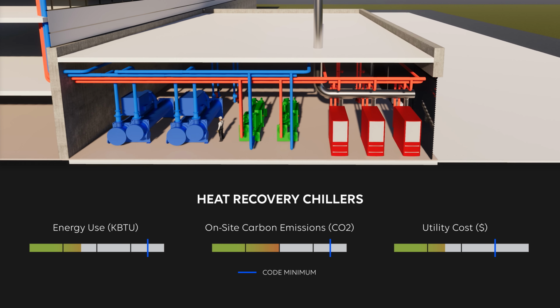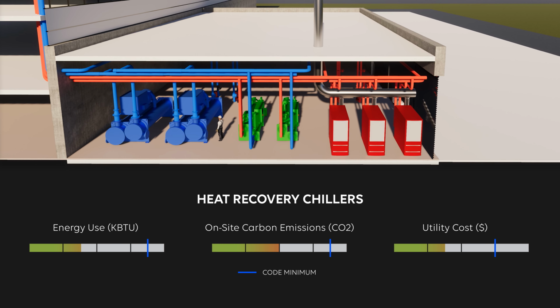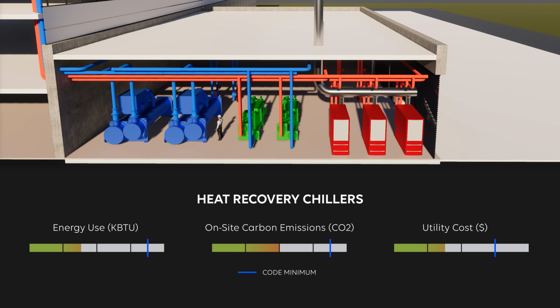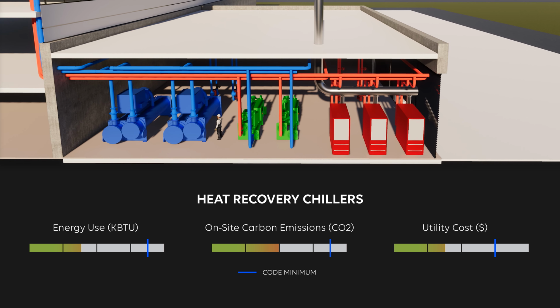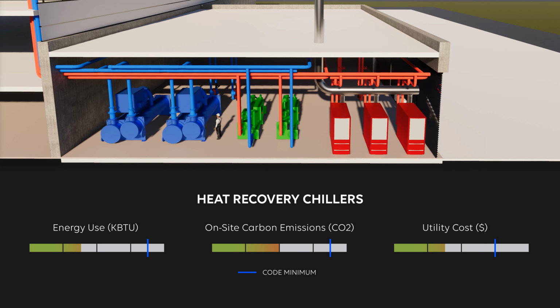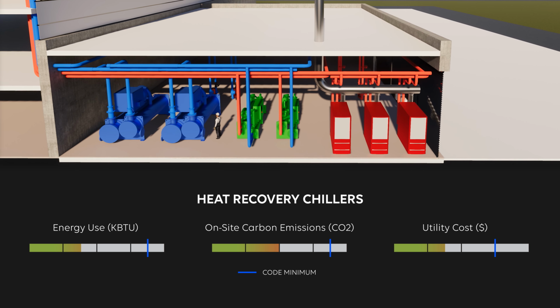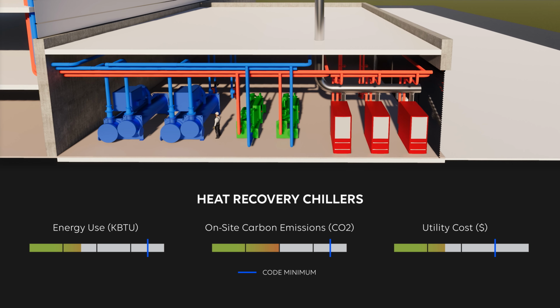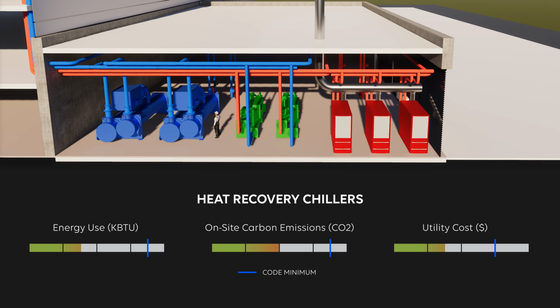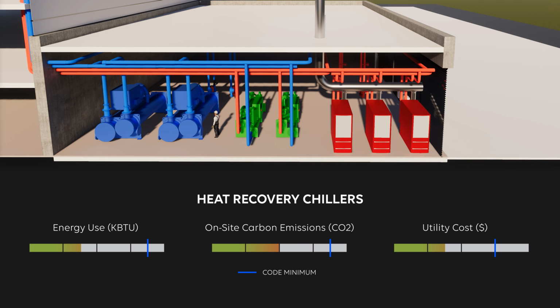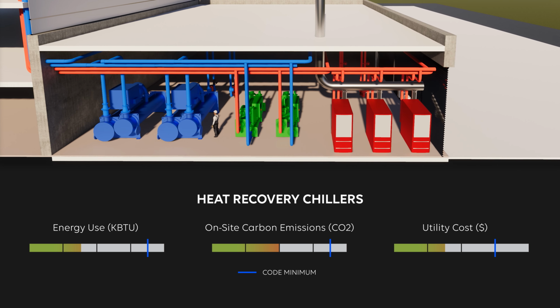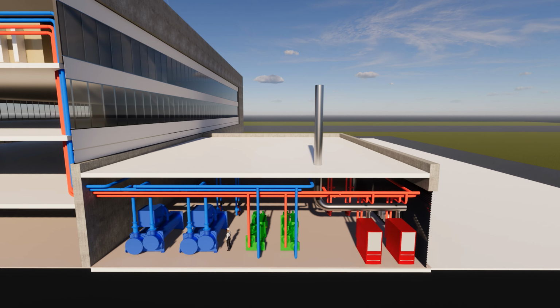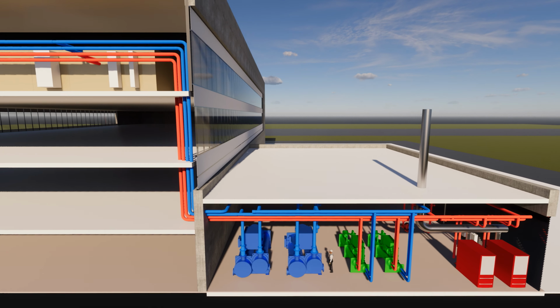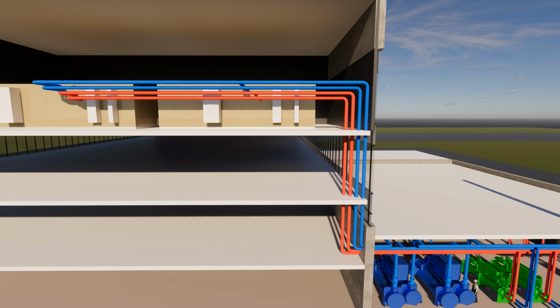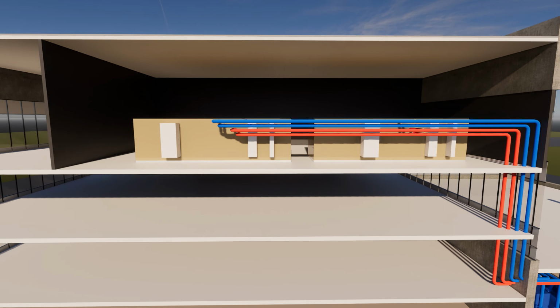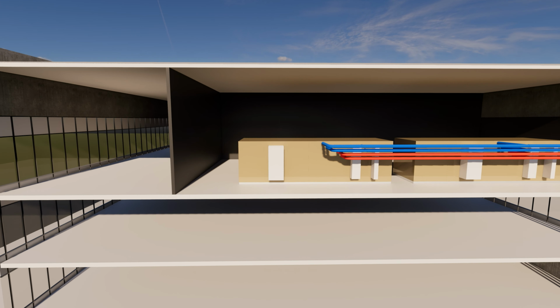These work by cooling down the chilled water loop and transferring the heat to the hot water loop for building heating. The dual purpose of the chiller allows it to achieve the high efficiencies required to reduce carbon emissions, utility costs, and energy use. A heat recovery chiller should be thought of as a heating device and be able to reduce the load on the boilers. The central utility plant distributes hot water to the hot water coils and chilled water to the chilled water coils. These are typically found in the air handlers, which condition the air supplied to the space.